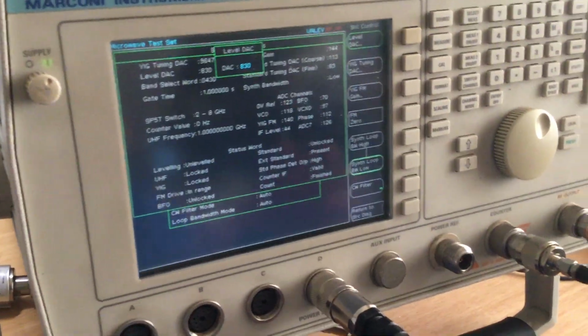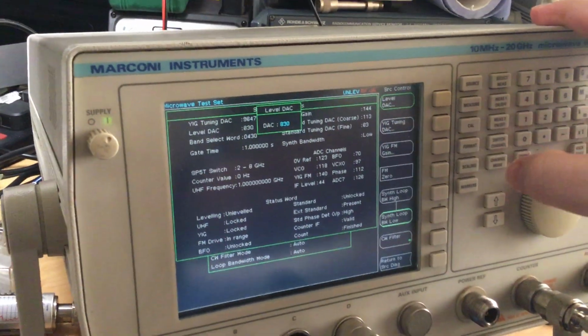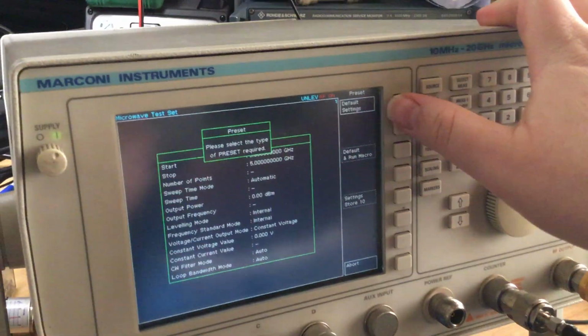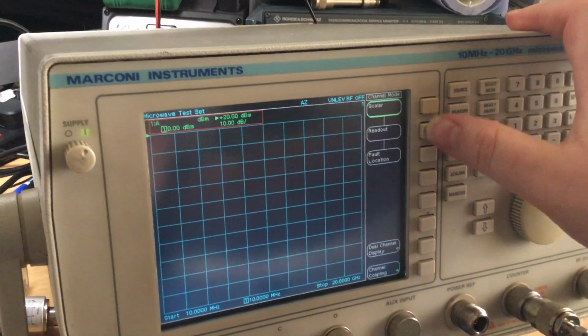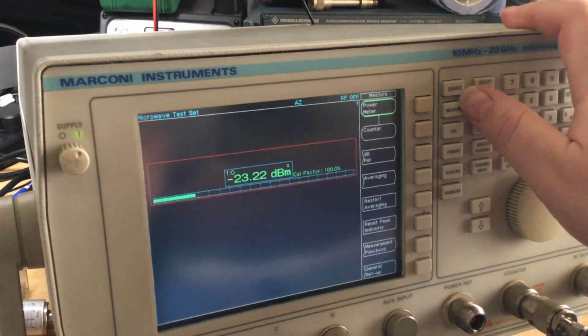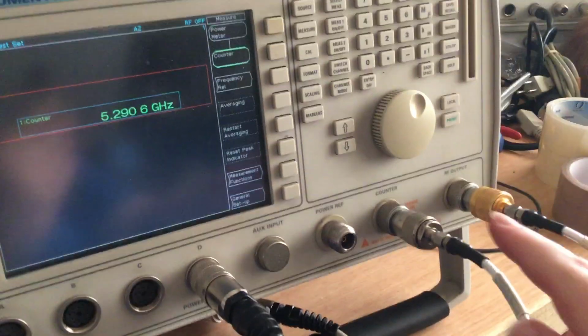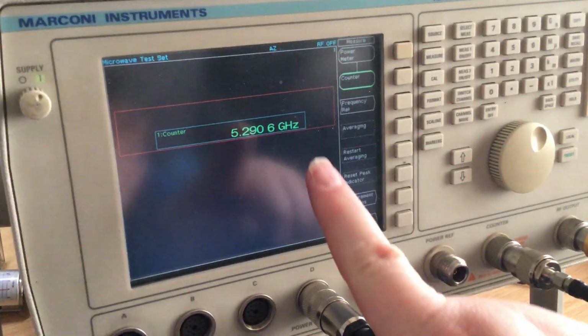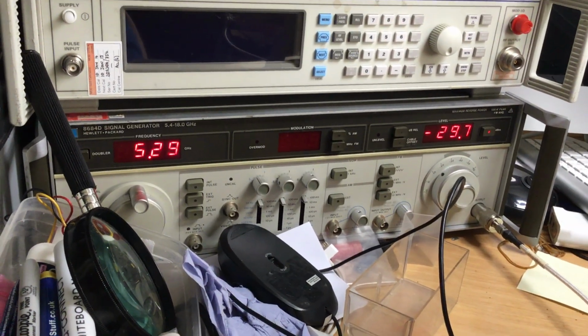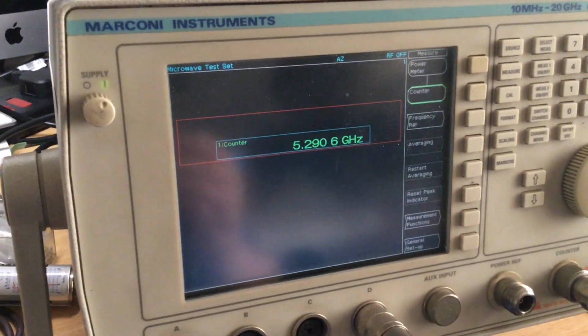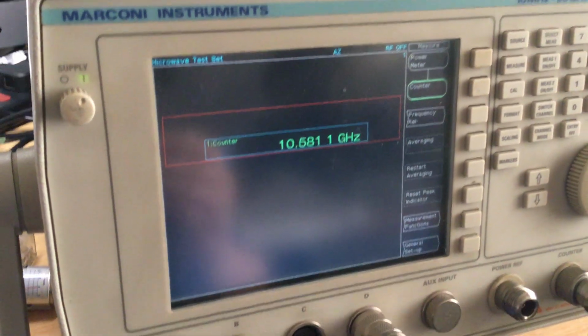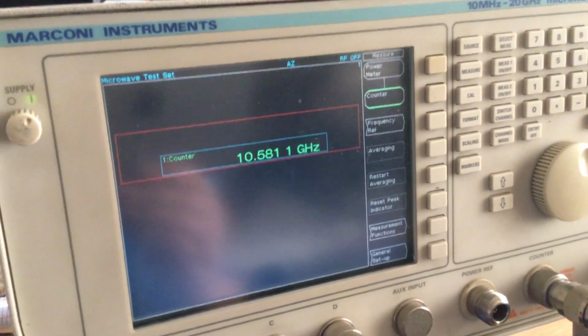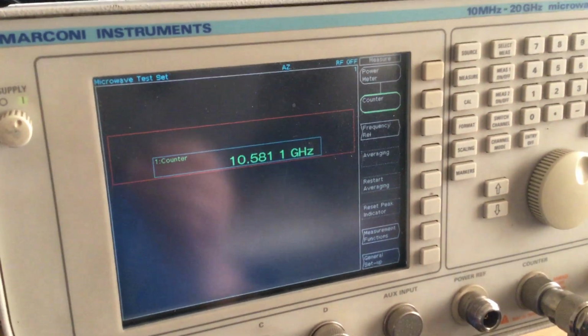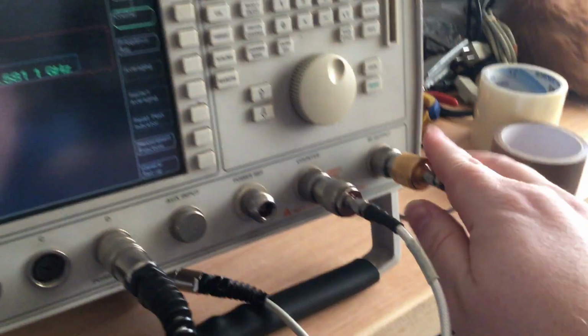Okay, so the next phase is to check the instrument calibration. Now we can do a calibration mode. So before we do that, I'll just do a preset. We'll go back to default settings. We'll go to readout for frequency, because I just want to check the frequency counter works. We'll go to measure counter, and at the moment I'm injecting here on this port 5.29 gigahertz, which it's correctly reading there. If we look at the signal generator, that's 5.29 gigahertz at minus 30 dBm, so it's quite sensitive. If I put the doubler on, so we've got to 10 gigahertz, we're on 10.59 gigahertz on the SIGGEN, and we're getting 10.591 gigahertz there. So that's obviously working. Right, so we know the frequency counter input's working.